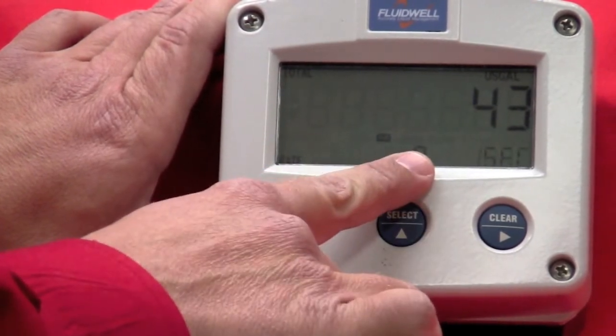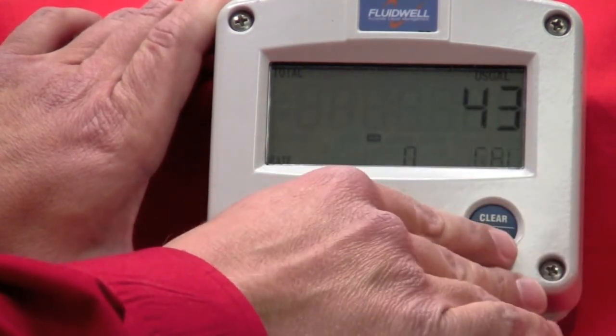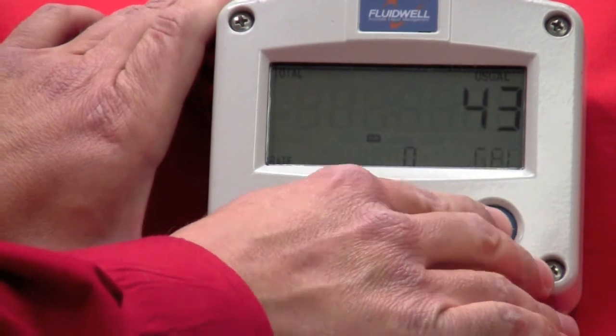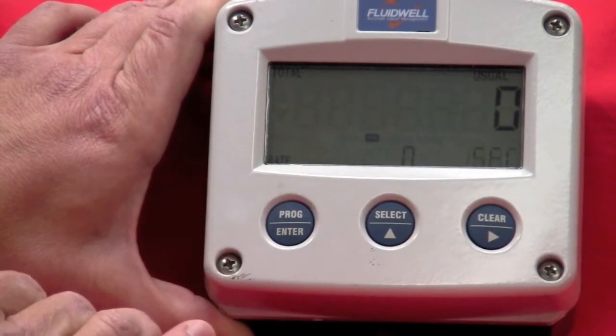If I push it again, it goes back to flow rate. To reset your totalizer while you're in the run mode, it's just push and release. I'm going to double-click the clear button, so I'll hit it once. It'll ask me to push clear to reset. If I hit it again, you'll see my total went back to zero.